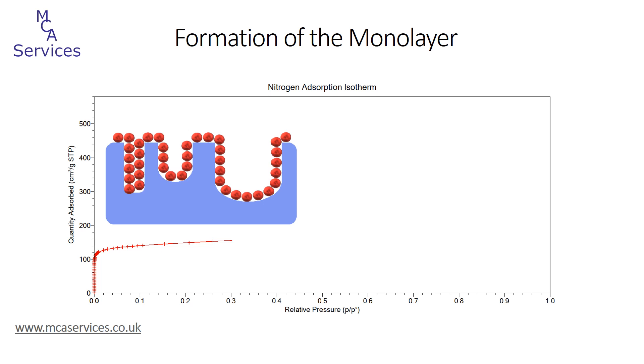As relative pressure increases, the adsorbate will continue to cover the external surface and also the walls of the meso- and macropores with a single layer of atoms. This complete coverage — a layer of adsorbate just one atom thick — is called the monolayer, and it's the volume of this that we are trying to establish when calculating surface area. For many samples, the monolayer is formed within the approximate range of 0.05 to 0.35 relative pressure, but this doesn't mean that this range always applies — we have to assess it for every individual analysis.